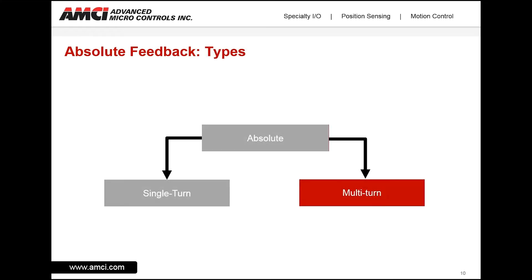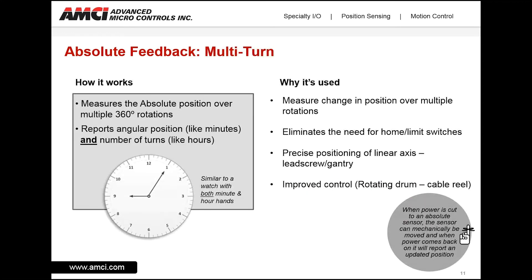For multi-turn rotary feedback, we measure the absolute position over multiple 360 degree rotations. It reports both angular position and the number of turns that have occurred since the shaft started rotating — similar to a watch with both a minute hand and an hour hand. These are used to measure change in position over multiple rotations, can eliminate the need for extra sensors such as home switches or limit switches to prevent over travel, and provide precise positioning of a linear axis such as a lead screw or gantry. Think of a rotating drum or a cable reel.